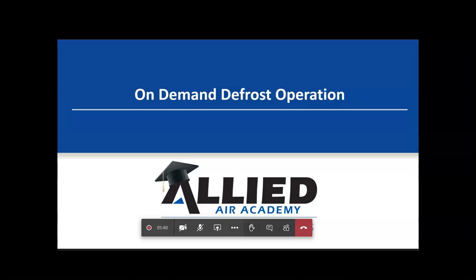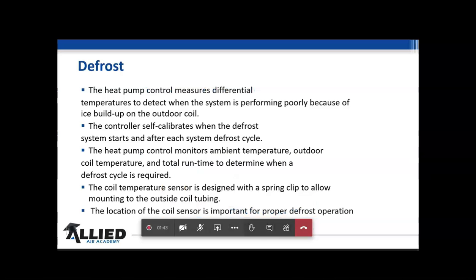So what we're going to talk about today, the heat pump, it measures differential temperatures to detect if the system is performing poorly because of ice buildup on the outdoor coil. So obviously that's what defrost does. The controller self-calibrates when the defrost system starts and after each system defrost cycle. So I'm going to say that again. The controller self-calibrates when the defrost system starts and after each system defrost cycle. That's going to be a key point here in just a few minutes whenever I start talking about some other things that I'm going to talk about.